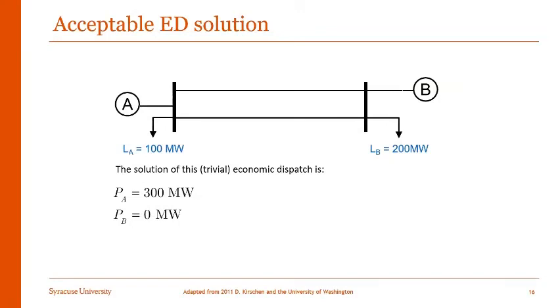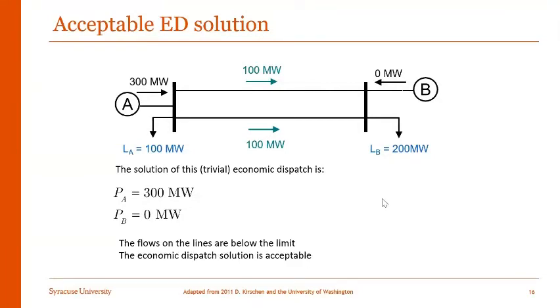In this case, the solution of economic dispatch gives us total production for generator A of 300 megawatts and total production for generator B of 0 megawatts. In both lines, we have a flow of 100 megawatts. This is trivial because we don't want to fire up the more expensive generator, so we're generating everything at generating station A. We observe that the flow of the lines are well below limit and the economic dispatch solution is accepted.